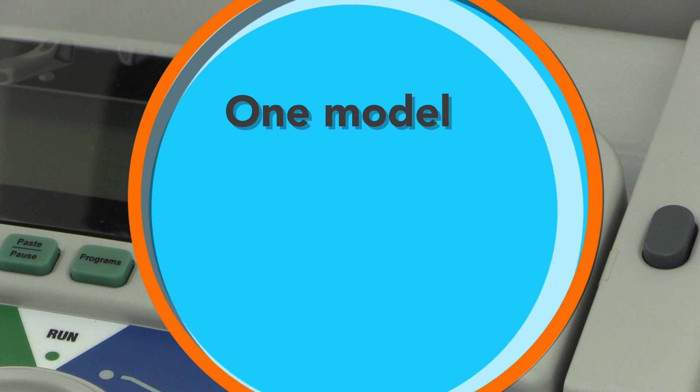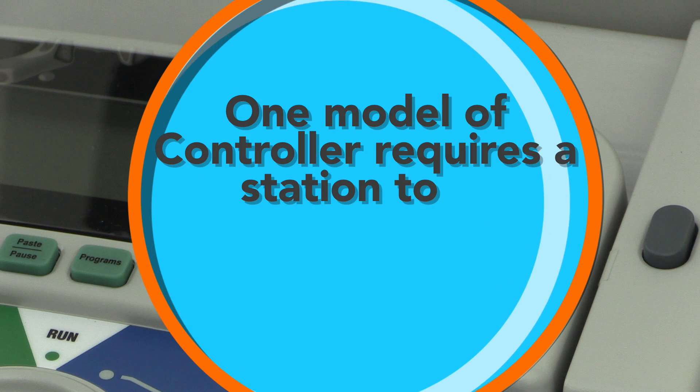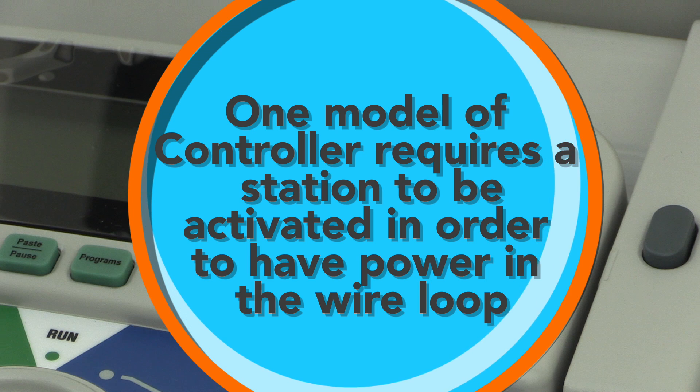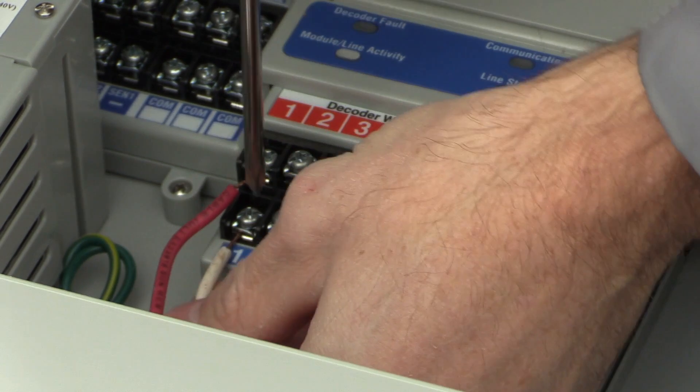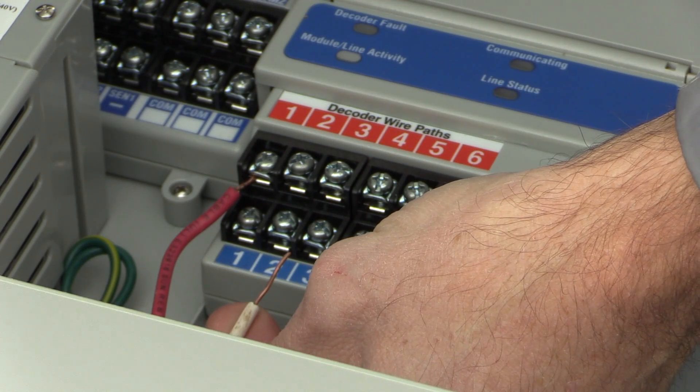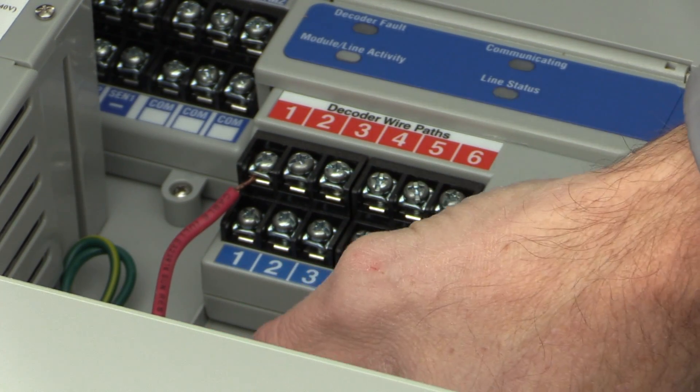Note that one model of controller requires a station to be activated in order to have power in the wire loop. A special note, if your two wire path loops back to the controller, you will need to disconnect one leg of the loop from the controller or power source to complete troubleshooting.